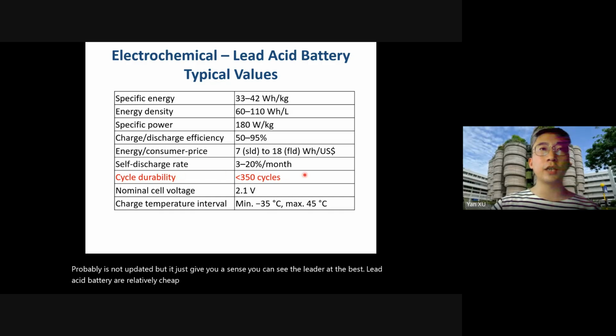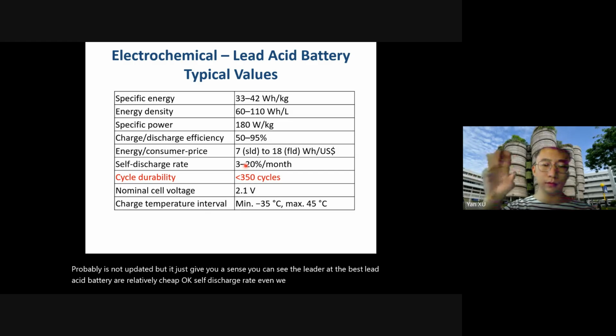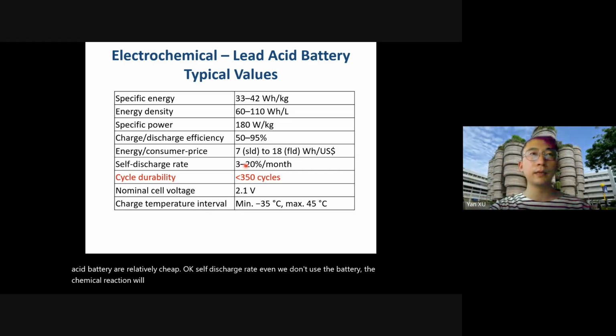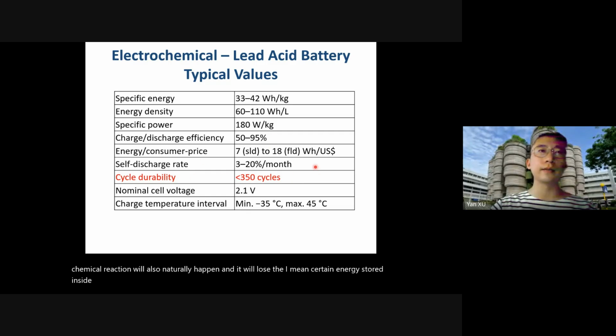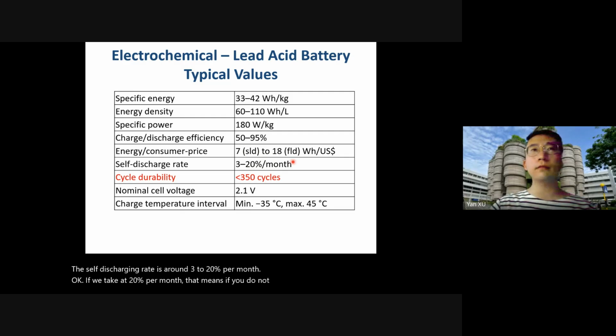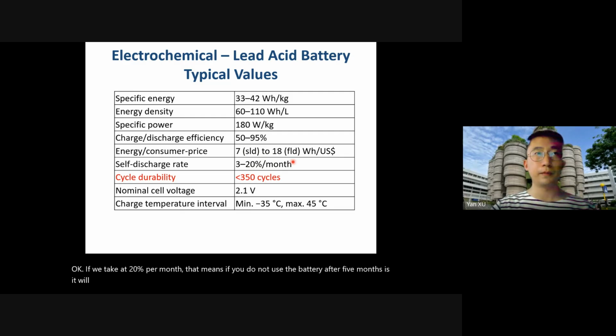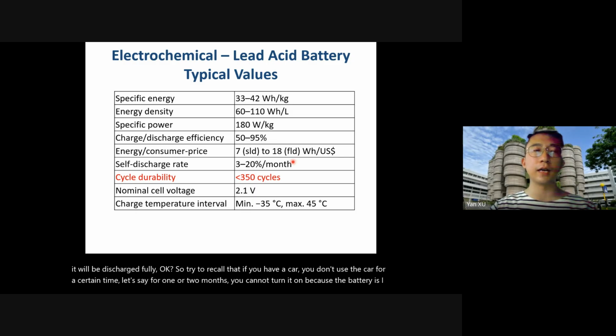Self-discharge rate: even if we don't use the battery, the chemical reaction will naturally happen, and it will lose certain energy stored inside. This is quantified as the self-discharge rate. For lead acid, this self-discharge rate is around 3 to 20% per month. If we take 20% per month, that means if you do not use the battery, after 5 months it will be fully discharged. Recall that if you have a car you don't use for 1 or 2 months, you cannot turn it on because the battery is fully discharged naturally.